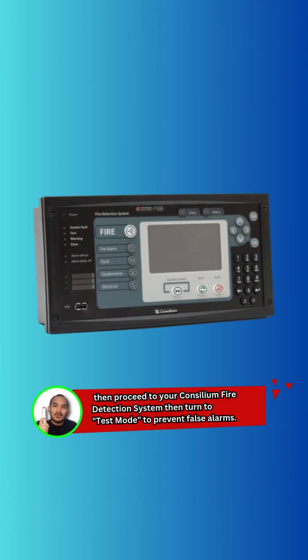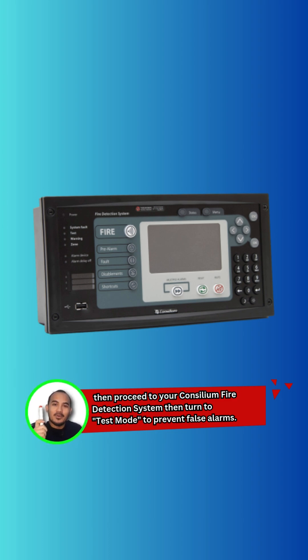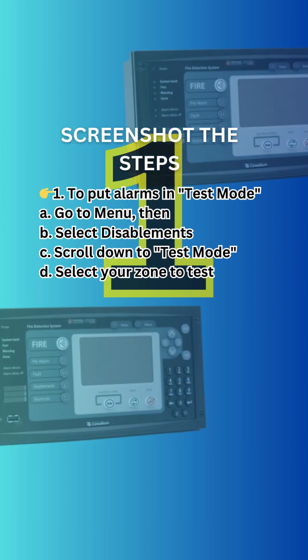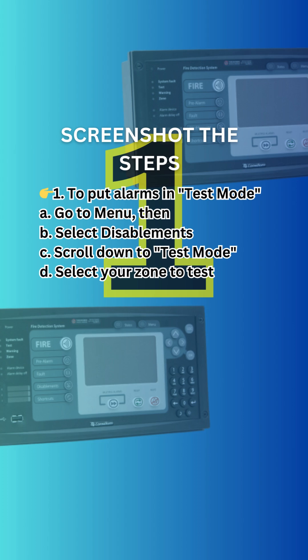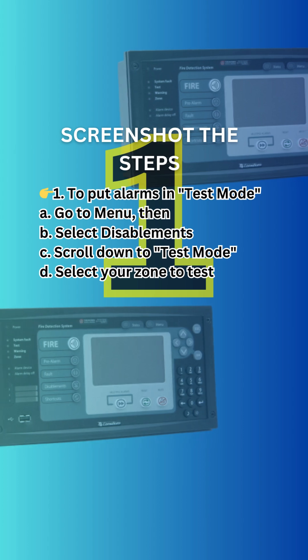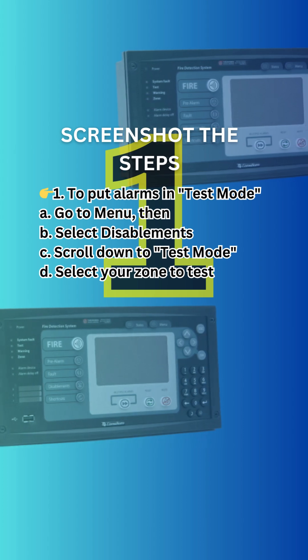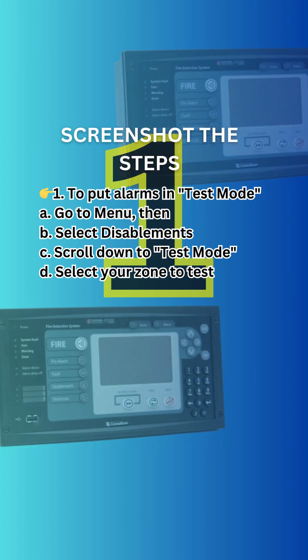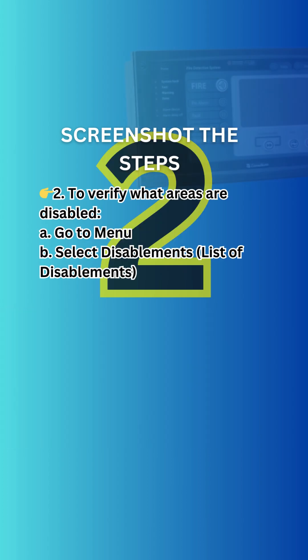Then proceed to your Consilium fire detection system and turn it to test mode to prevent false alarms. To put alarms in test mode, go to menu, then select disablements, scroll down to test mode, and select your zone to test.